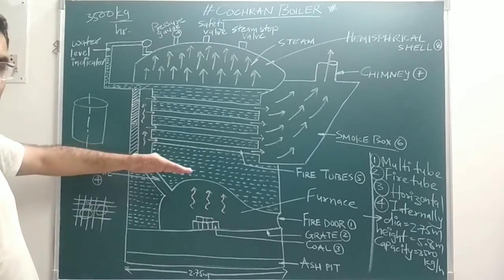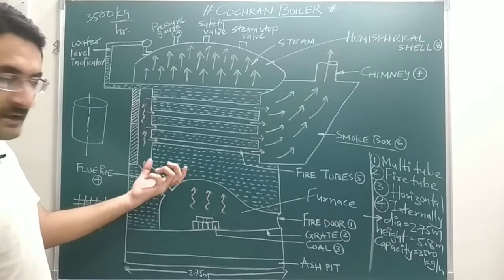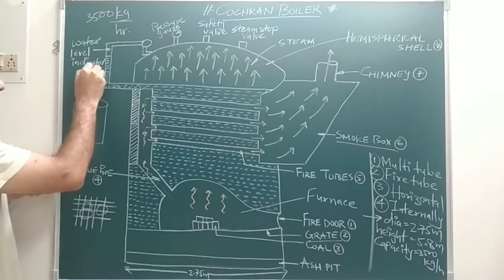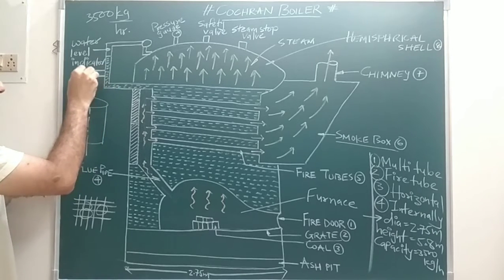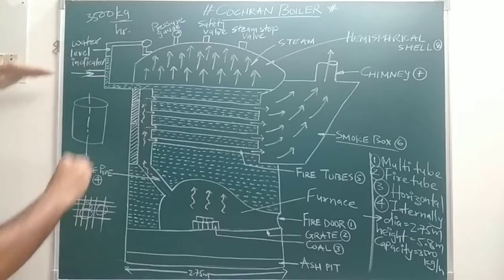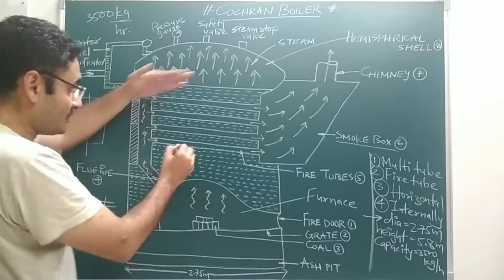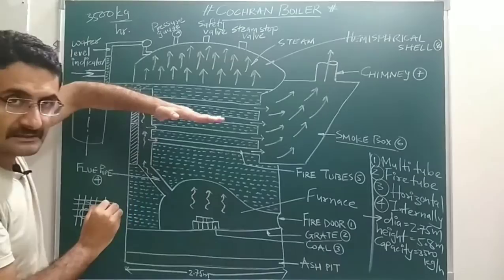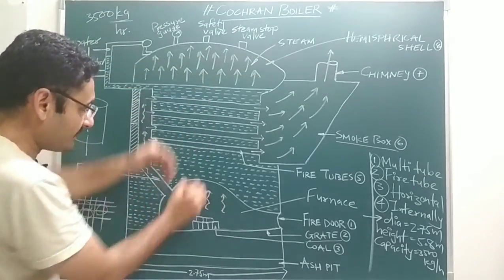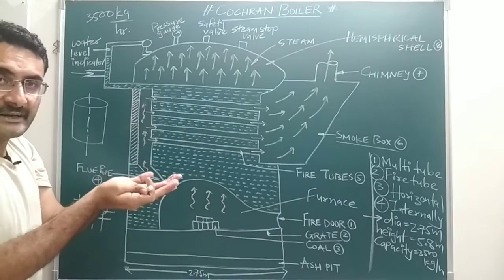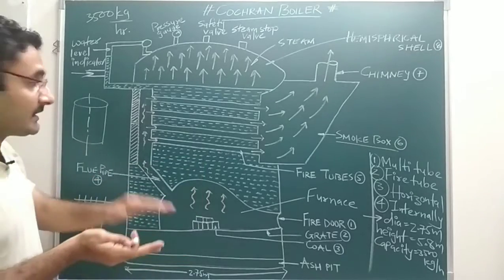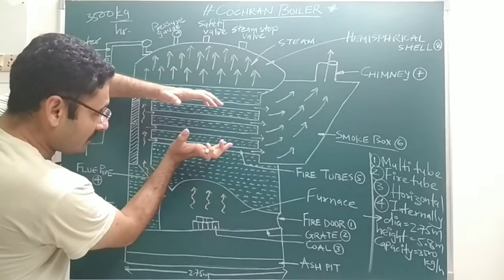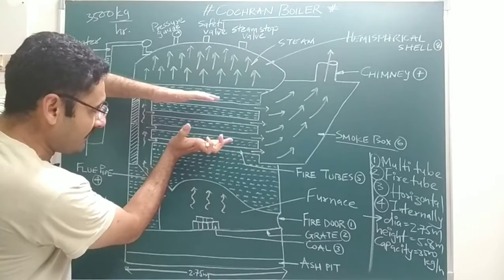The circulation of water in this boiler is natural. We are not using any type of pump, so forced circulation is not present — only natural circulation. Cold water is passed through the feed check valve. Cold water has higher density, so it moves in the downward direction and comes in contact with the fire tubes, where it is heated and converted into hot water.